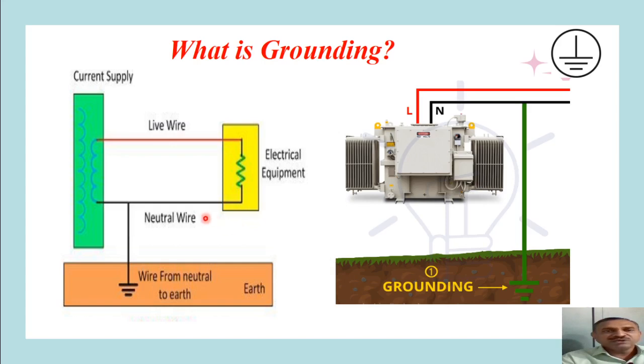Now what is grounding is more clear by referring to these two diagrams. Here we have shown a supply system which is having live and neutral wire, electrical equipment. The neutral wire at the source itself is being grounded, that is connected to the earth through the earth electrodes. It means that neutral point at the power supply system distribution point will be at 0 potential.